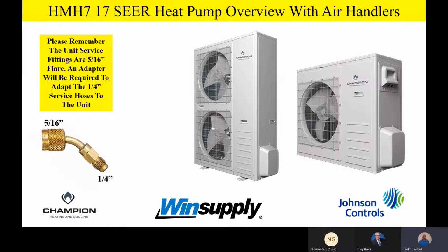Even though it has a similar look, these are not mini splits, and we're going to hook them up just like a regular heat pump with just a suction line. We're going to insulate that suction line like we always do, and we're going to have probably about a 3/8 liquid line typically. So just a regular heat pump. The other thing that I really like about these, the fact that it's modulating, gives you lots of comfort, but also we've got some nice long line length applications. Depending on the tonnage, we can actually go up to like 260 feet in some applications. I think the 2 ton model maybe has a limitation of maybe 160 feet or maybe 180 feet.